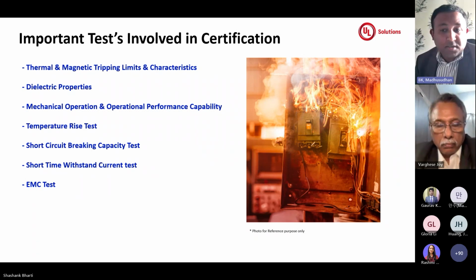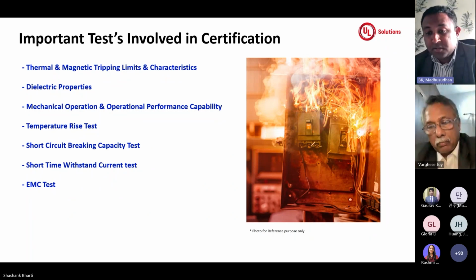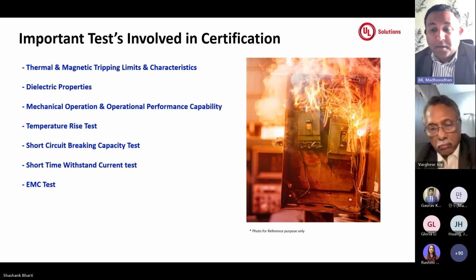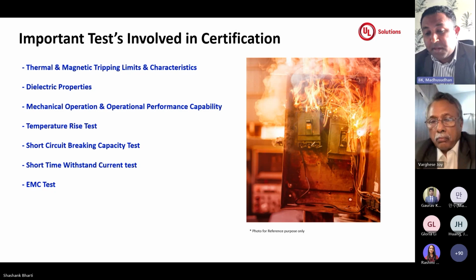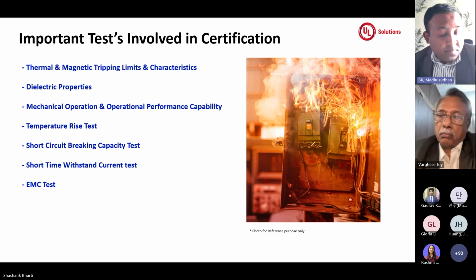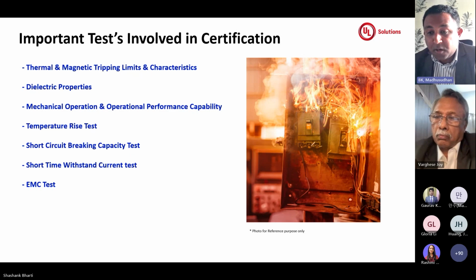And in addition to all these tests, there will be some more tests conducted on breakers, especially on the terminals. For terminal testing, we normally call it secureness and pullout. Basically, the conductors and the torque declared by the manufacturers will be applied. Breakers are normally declared with different conductor sizes, from minimum range to maximum range, that are going to be put up in the field. So based on the range declared by the manufacturer and the torque value, in the secureness test the conductor will be tightened to that particular torque, and a weight based on the standard requirement will be put on the conductors, and the breaker terminals will be put under this test.